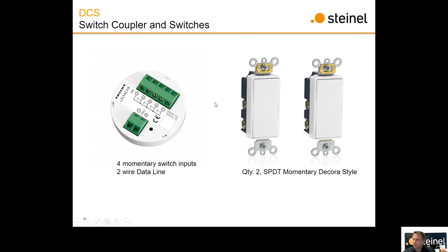The final point I'd like to make on the DCS is that it's plug and play. As I mentioned at the top, it's code compliant out of the box. You just wire it up with low voltage, non-polarized, stab-in 18 gauge wires, and basically it's already working before the commissioning agent arrives. So it's really handy because on day 1, before the commissioning agent is able to get there, you've already got it set up and working. You may just have some tweaks at commissioning time.